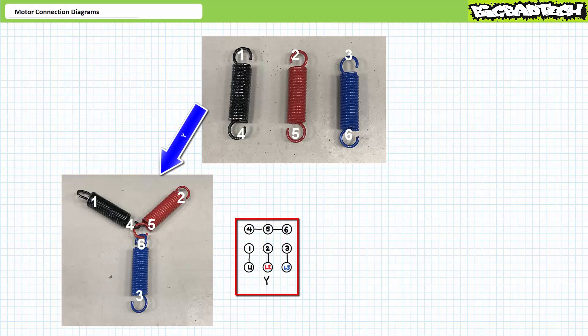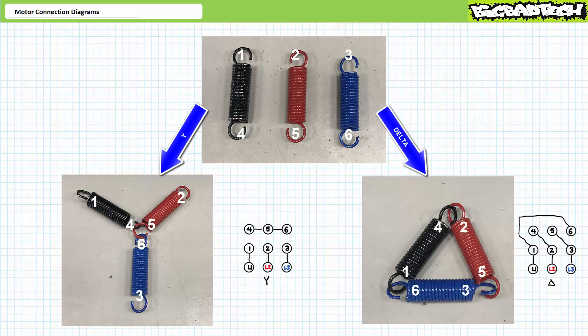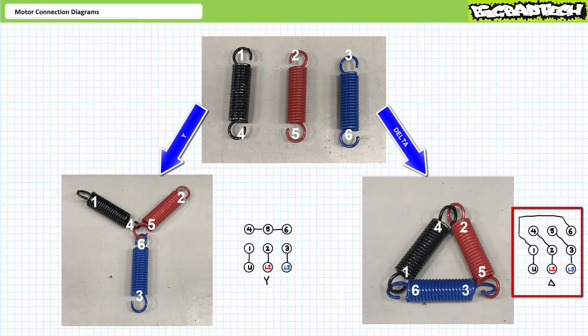A motor connection diagram for a six-lead motor in Y configuration: L1 to 1, L2 to 2, L3 to 3, and 4, 5, and 6 tied together. When configured as deltas, terminal 4 is tied with 2, 5 is tied with 3, and 6 is tied with 1. Primary voltage L1, L2, and L3 is connected to the conjoined terminals 1&6, 2&4, and 3&5. In the delta configuration, the windings would experience the higher line-to-line voltage. The connection diagram: L1 to 1 and 6, L2 to 2 and 4, and L3 to 3 and 5.